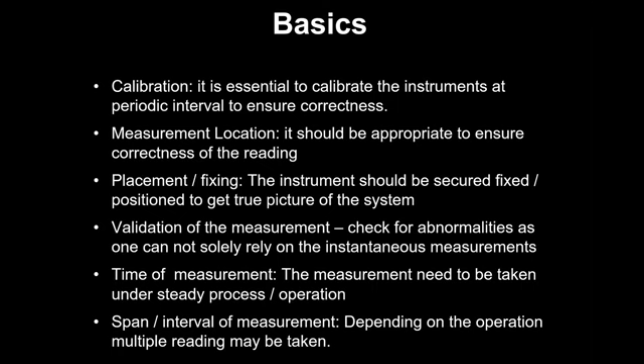I have been in this field for 30 years. We have seen all kinds of people. That is really short-sightedness, because we do so many measurements. So it is always better to have the instrument calibrated. Our instruments are normally calibrated once a year. But if we have a doubt about some readings which we feel are not matching, or the client feels there is a problem somewhere, we try to verify against another instrument, or we send it for recalibration even in less than a 1 year period.